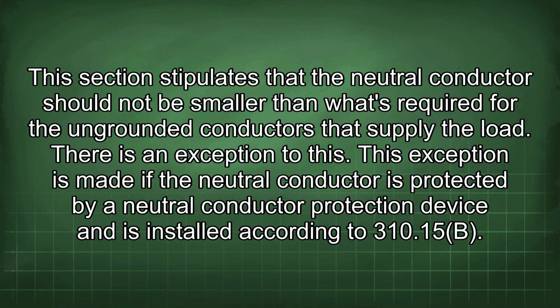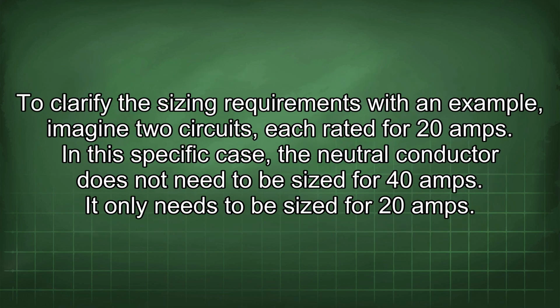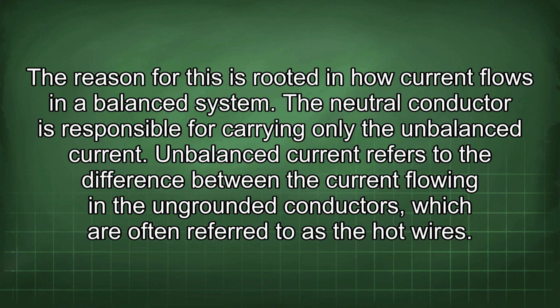to 310.15(B). To clarify the sizing requirements with an example, imagine two circuits, each rated for 20 amps. In this specific case, the neutral conductor does not need to be sized for 40 amps. It only needs to be sized for 20 amps. The reason for this is rooted in how current flows in a balanced system. The neutral conductor is responsible for carrying only the unbalanced current.